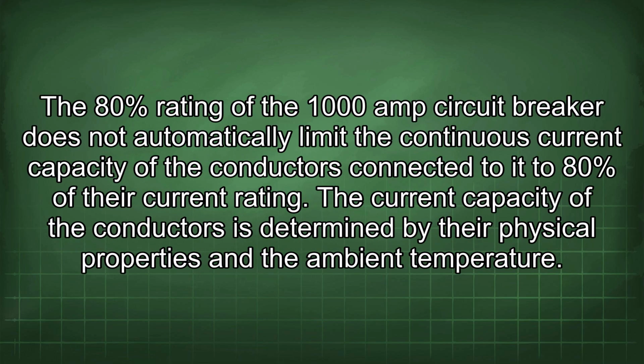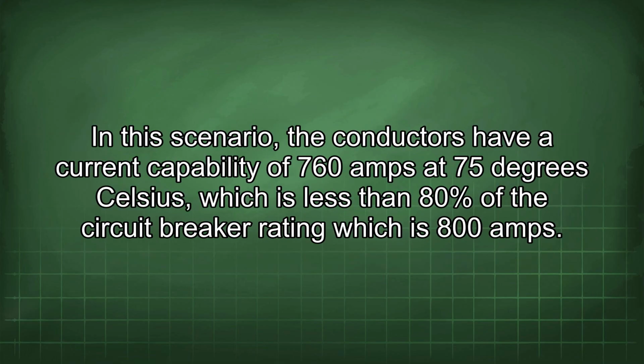The 80% rating of the 1000 amp circuit breaker does not automatically limit the continuous current capacity of the conductors connected to it to 80% of their current rating. The current capacity of the conductors is determined by their physical properties and the ambient temperature. In this scenario, the conductors have a current capability of 760 amps at 75 degrees Celsius, which is less than 80% of the circuit breaker rating, which is 800 amps.